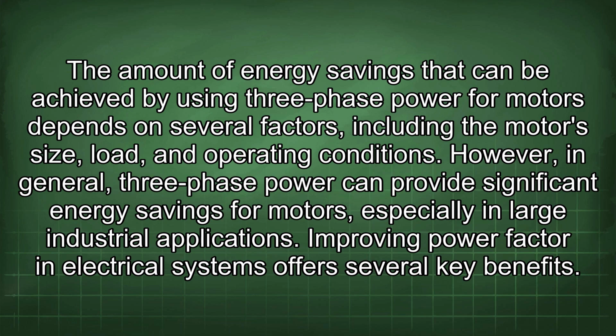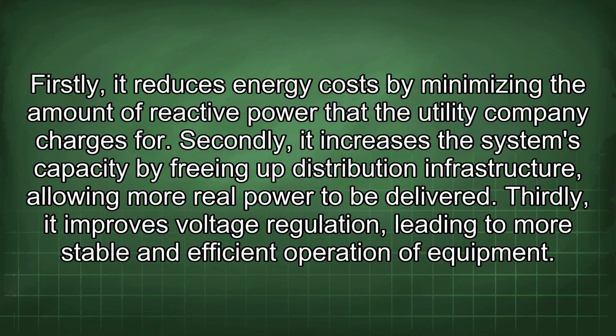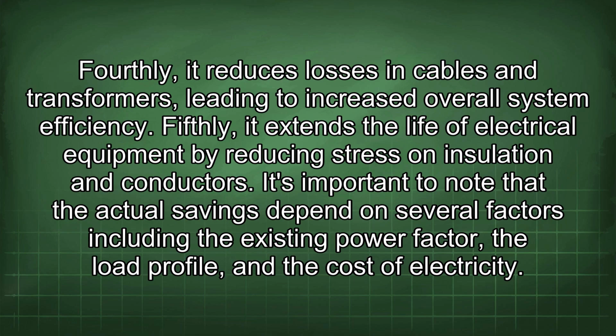Improving power factor in electrical systems offers several key benefits. Firstly, it reduces energy costs by minimizing the amount of reactive power that the utility company charges for. Secondly, it increases the system's capacity by freeing up distribution infrastructure, allowing more real power to be delivered. Thirdly, it improves voltage regulation, leading to more stable and efficient operation of equipment. Fourthly, it reduces losses in cables and transformers, leading to increased overall system efficiency. Fifthly, it extends the life of electrical equipment by reducing stress on insulation and conductors.